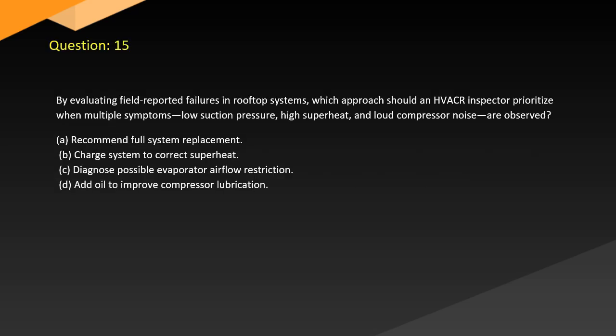Question 15. By evaluating field-reported failures in rooftop systems, which approach should an HVACR inspector prioritize when multiple symptoms are present? Low suction pressure, high superheat, and loud compressor noise are observed. A. Recommend full system replacement. B. Charge system to correct superheat. C. Diagnose possible evaporator airflow restriction. D. Add oil to improve compressor lubrication.